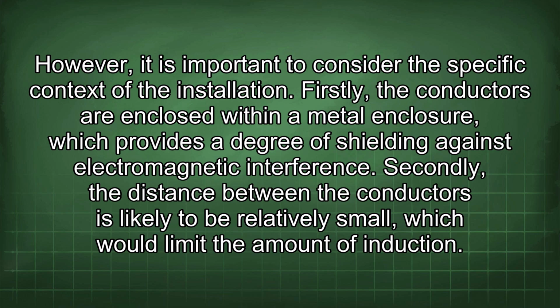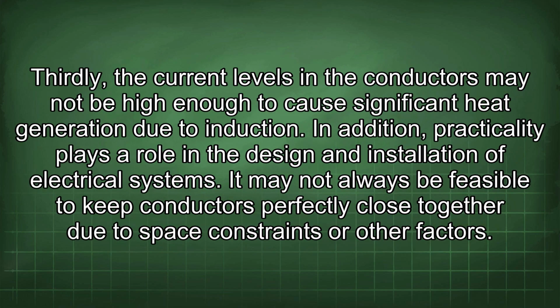Firstly, the conductors are enclosed within a metal enclosure, which provides a degree of shielding against electromagnetic interference. Secondly, the distance between the conductors is likely to be relatively small, which would limit the amount of induction. Thirdly, the current levels in the conductors may not be high enough to cause significant heat generation due to induction.